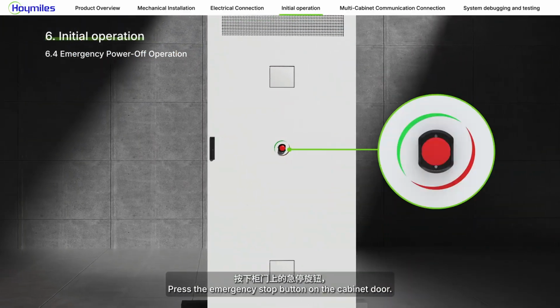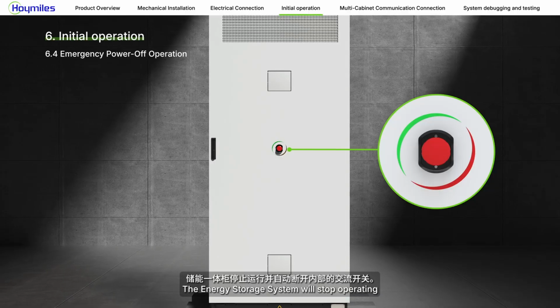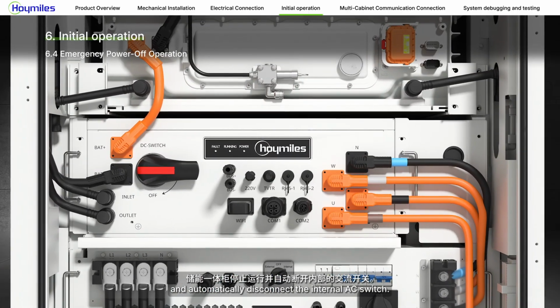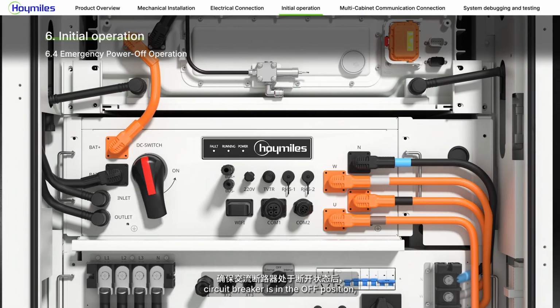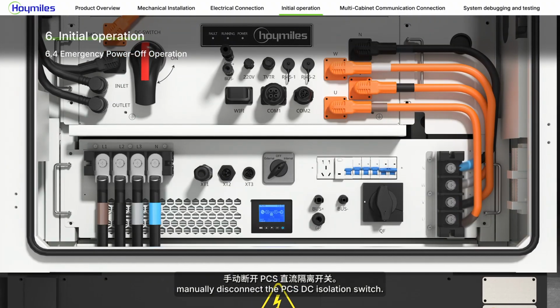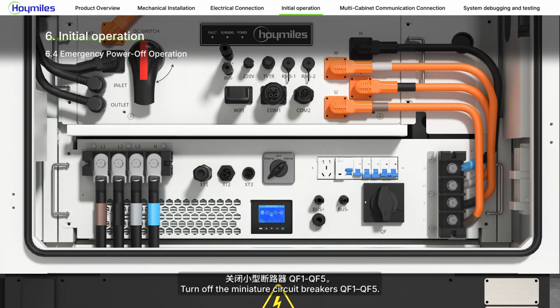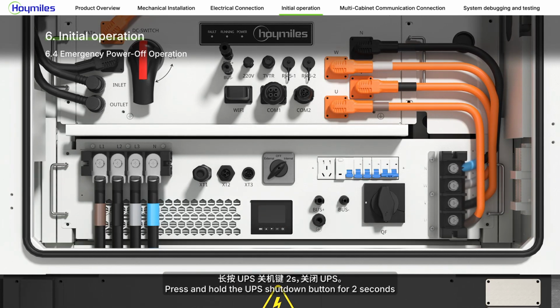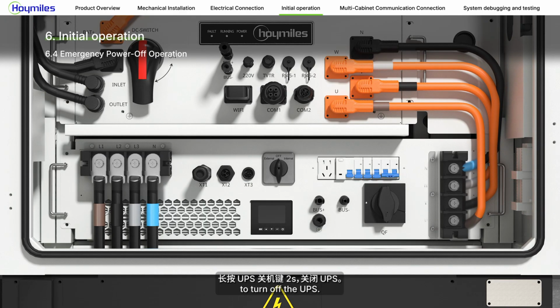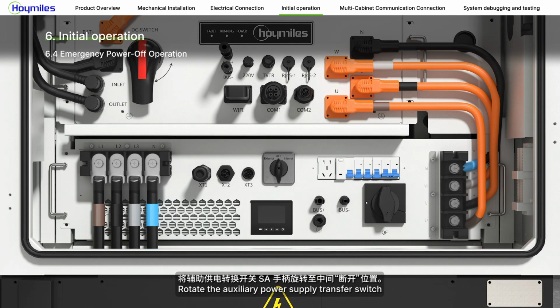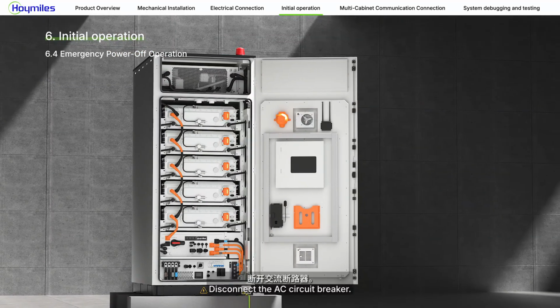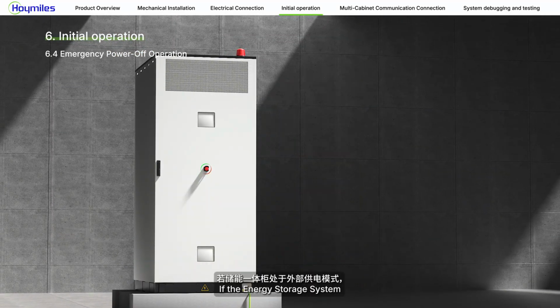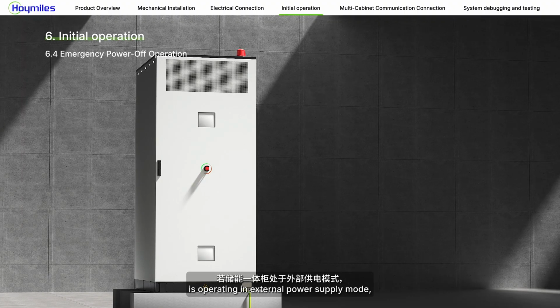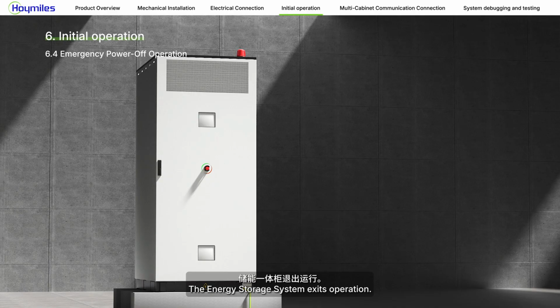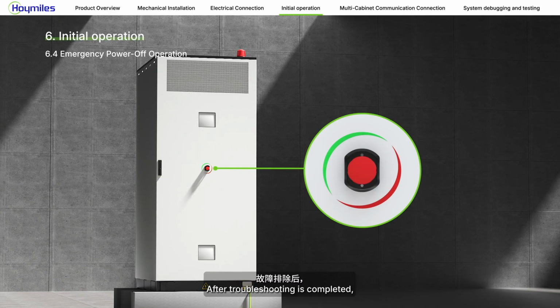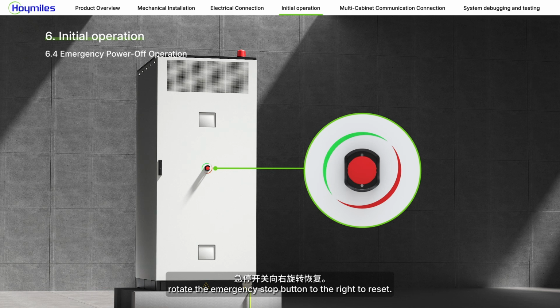Press the emergency stop button on the cabinet door. The energy storage system will stop operating and automatically disconnect the internal AC switch. After ensuring that the AC circuit breaker is in the off position, manually disconnect the PCS DC isolation switch. Turn off the miniature circuit breakers QF1 to QF5. Press and hold the UPS shutdown button for 2 seconds to turn off the UPS. Rotate the auxiliary power supply transfer switch SA handle to the middle off position. Disconnect the AC circuit breaker. If the energy storage system is operating in external power supply mode, disconnect the external power supply. The energy storage system exits operation. After troubleshooting is completed, rotate the emergency stop button to the right to reset.